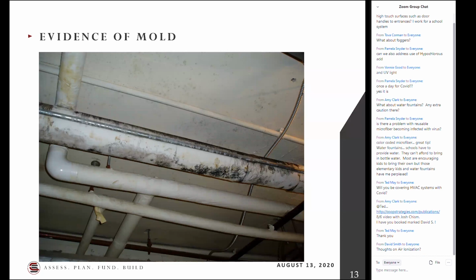and you'll see that linear pattern on the ceiling tiles, or maybe you'll see it scattered out where there's bends or elbows, or maybe where there's fire sprinklers above the ceiling. But that's an incredibly difficult problem to deal with in our climate, where it can be 140 above a suspended ceiling, and you've got 45-degree chilled water, or even room temperature water in a fire sprinkler system. The temperature difference is such that you can have condensation without too much trouble.